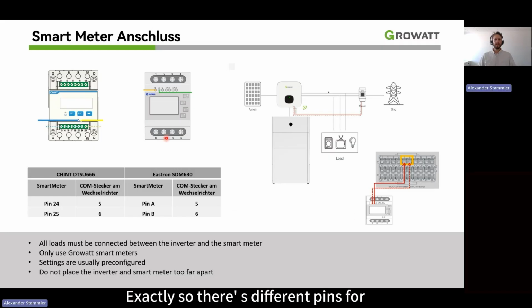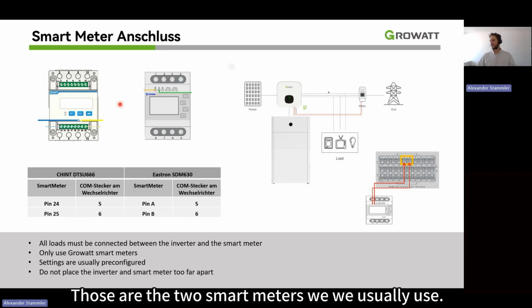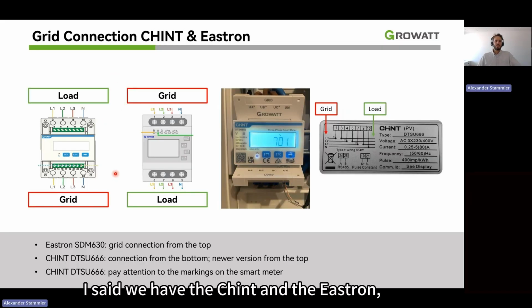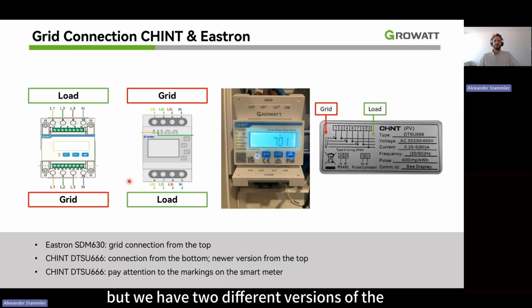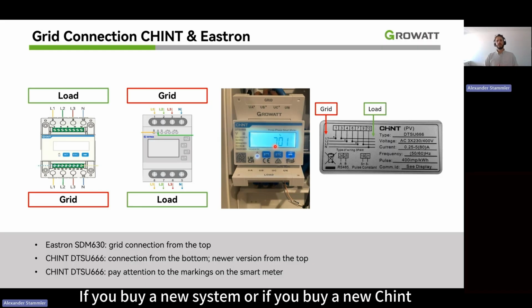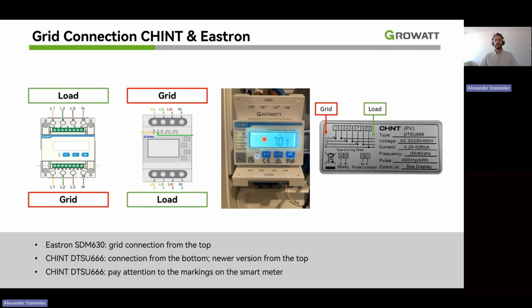Exactly. So there are different pins for the Chint and the Eastron. Those are the two smart meters we usually use. I said we have the Chint and the Eastron, but we have two different versions of the Chint right now in the field. One where the load is connected from top, and one where the load is connected from bottom. So this one is the newer one. If you buy a new system or a new Chint, you might get this one where it's written on. On the old one, it's not written where to connect the grid or the load.